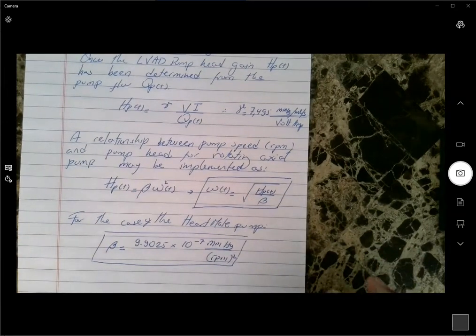So why is it important to calculate the RPM? Well, because this is one of the variables that is directly attainable, directly measurable through sensors as simple as optical sensors. You can actually measure the RPM of a pump, and that number can be brought back into the display of the LVAD system and used as part of a control system to control the speed of the pump.